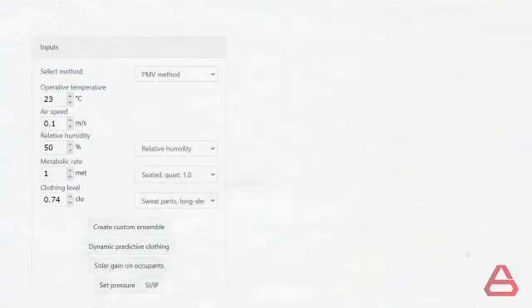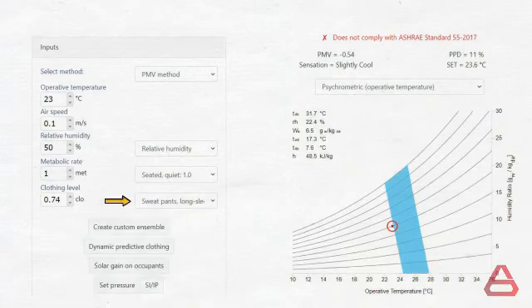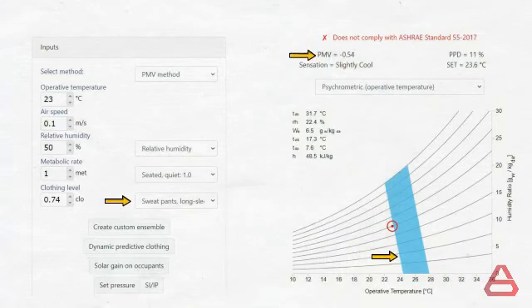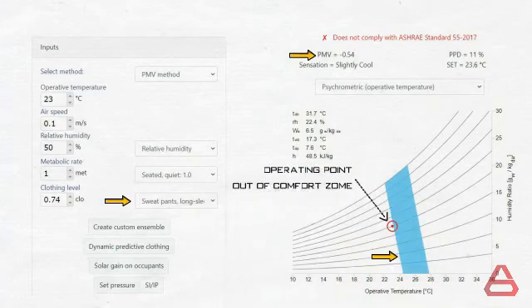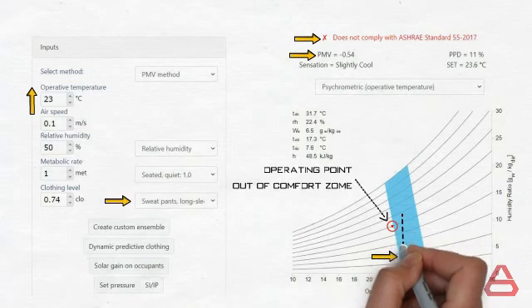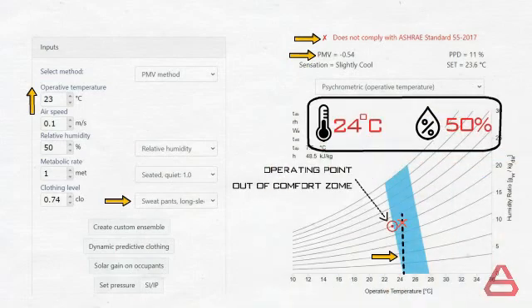Changing the clothing level from typical indoor clothing to long sleeve shirts with sweatpants, you can see how the comfort zone has shifted to the right. The PMV dropped from minus 0.08 to minus 0.54, and the operating point is now out of the comfort zone and no longer compliant with ASHRAE Standard 55. Therefore, a higher temperature is required to achieve comfort. Raising the temperature to 24 degrees Celsius brings the operating point back into the comfort zone, giving new design conditions of 24 degrees Celsius and 50% relative humidity. With the help of this tool, determining the needed design conditions is a fairly easy task.